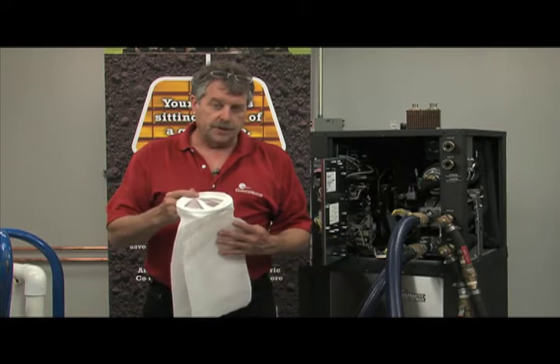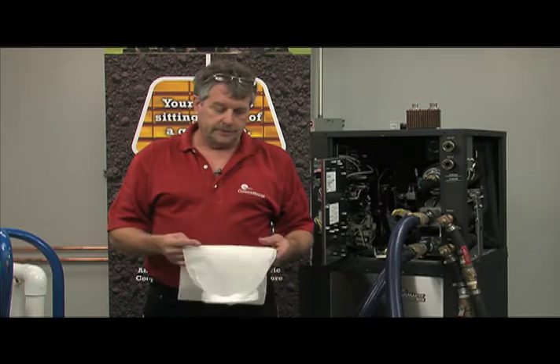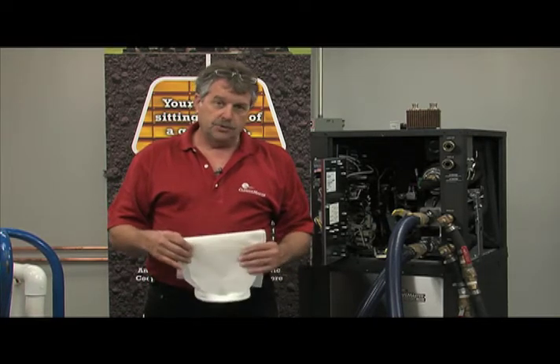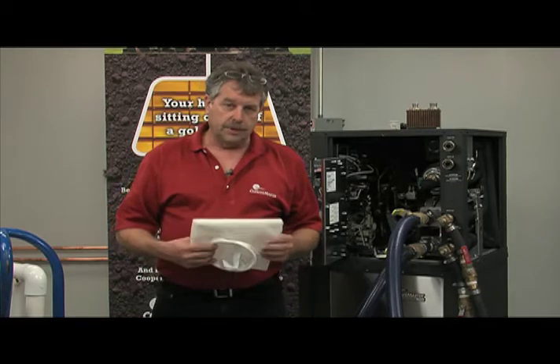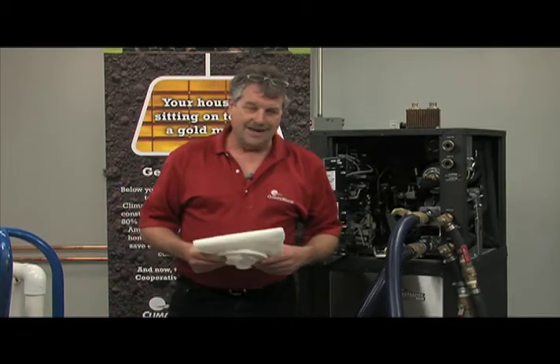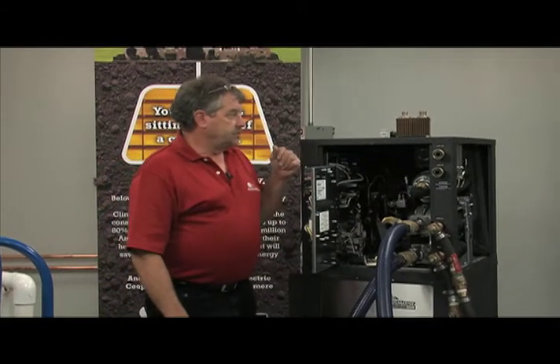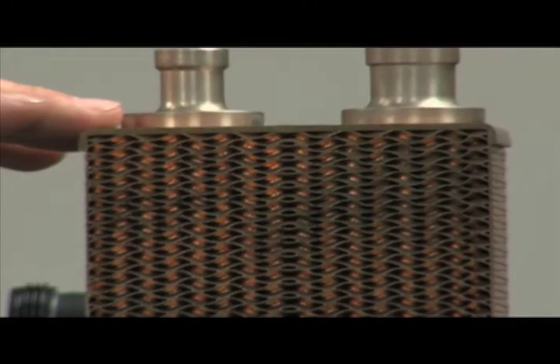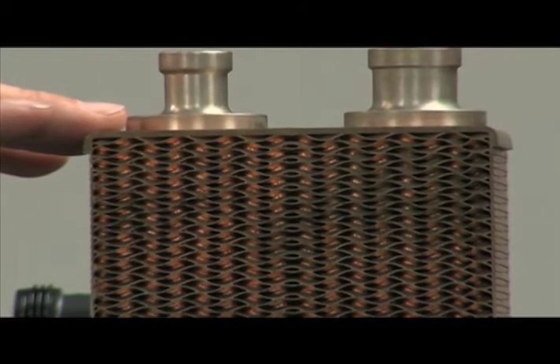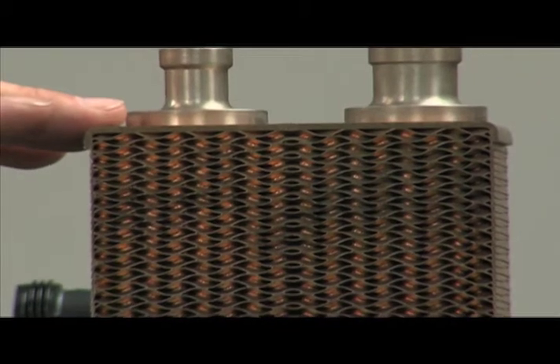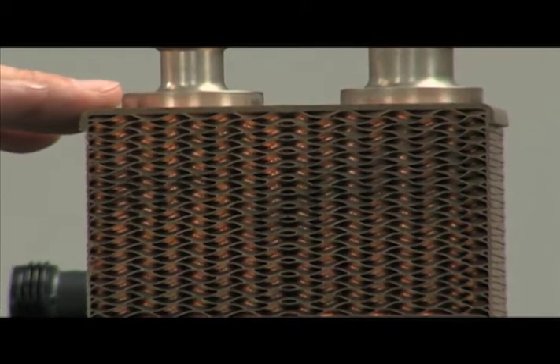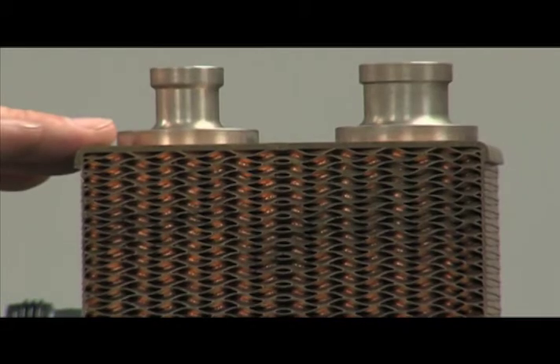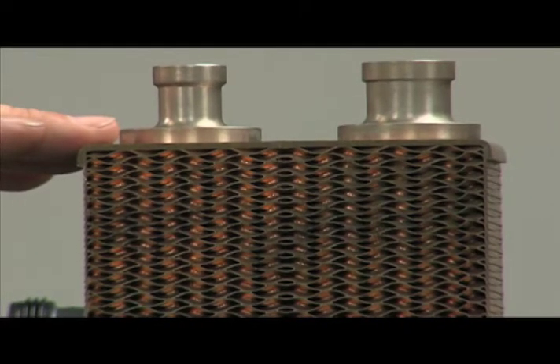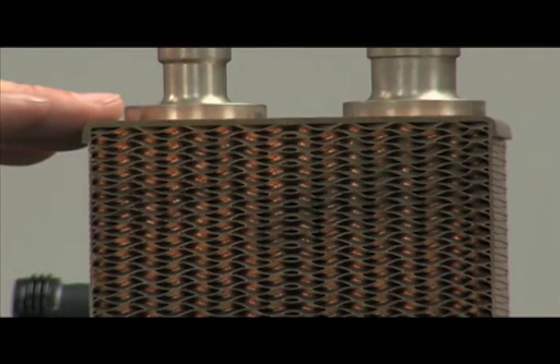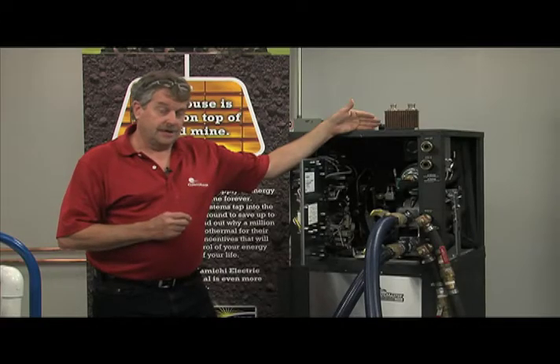There are other filtration methods you could utilize, a Y strainer. I've seen some people use pool filters, but make sure that you're taking safeguards and some measures against contamination, debris that's in loop fields oftentimes. On the Trilogy product in particular, we use a braze plate heat exchanger, and you can see that the water passageways are very, very tiny. It wouldn't take terribly much to impact them, which is going to inhibit the flow. And because it's surrounded by refrigerant, you could actually compromise that heat exchanger and severely damage that unit.